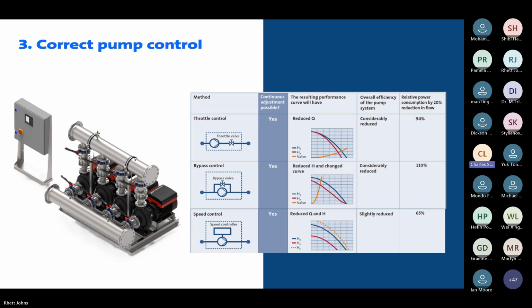Yeah, and there are various ways of controlling pumps. So you can see on the right the common methods consisting of throttle control, bypass control, and speed control. The first two are more traditional methods. So throttle control is where we're using a valve to limit the flow. But there are two inherent problems with this, and that is the unnecessary power consumption and excessive pressure in the system.